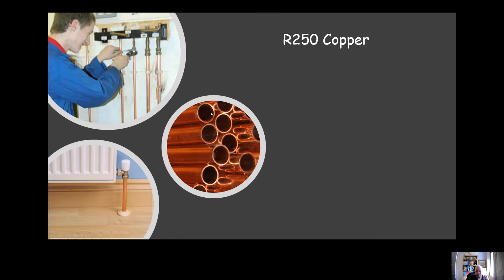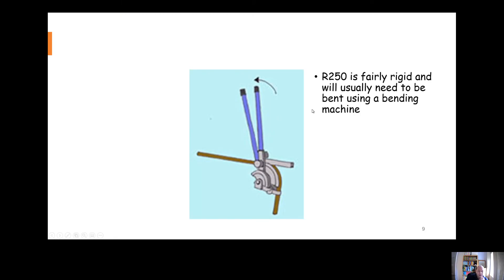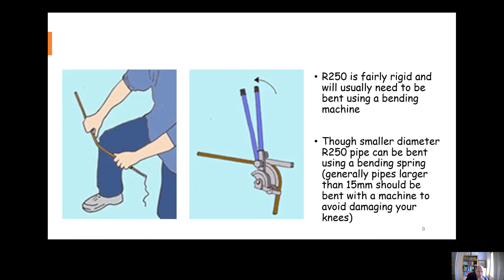R250 is the most commonly used type. The sizes can vary from 12mm up to 54mm, though the sizes that we are most likely to use are 15mm, 22mm, and 28mm, so it's worth making sure we remember these. R250 can be plated with chromium, which gives it a nice shiny finished look. R250 is considered to be half hard, so it's quite rigid. You should only really bend it using a bending machine, or very occasionally if it's a smaller bore R250 pipe, you could bend it using a bending spring.